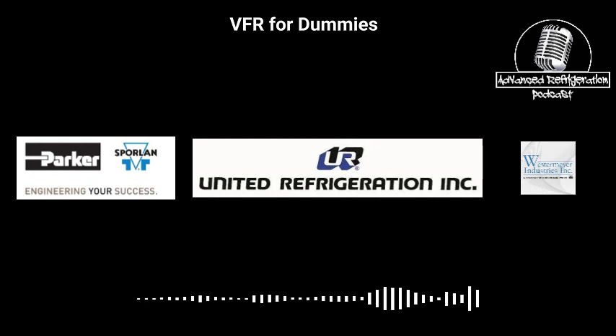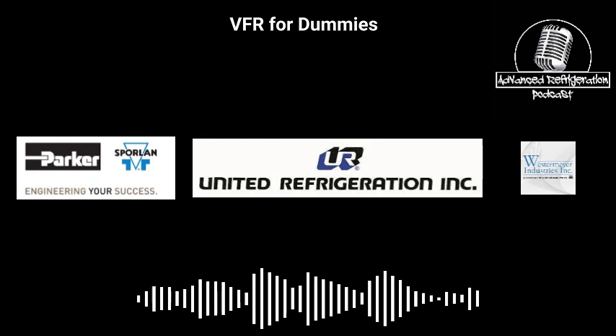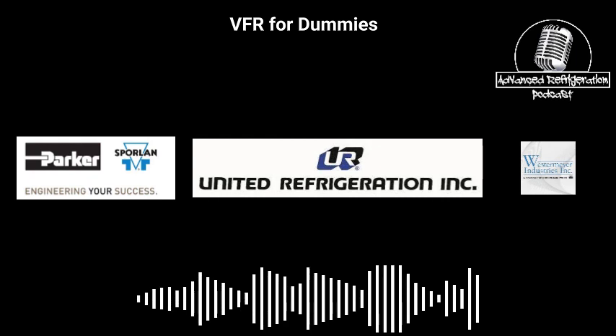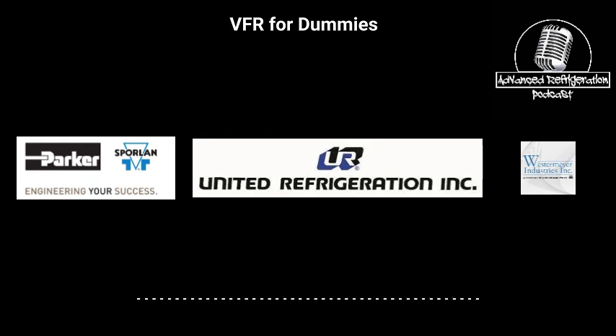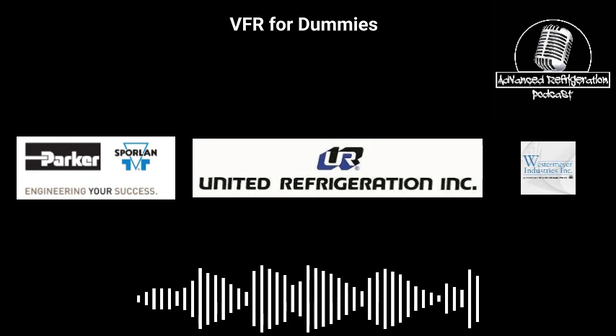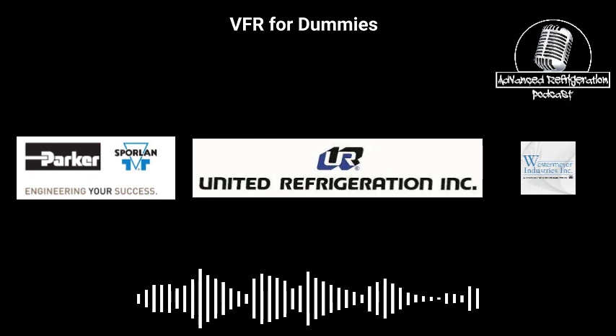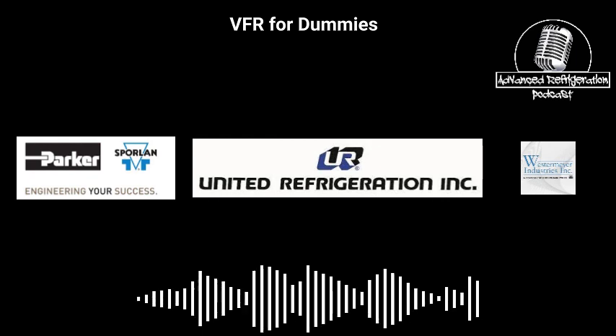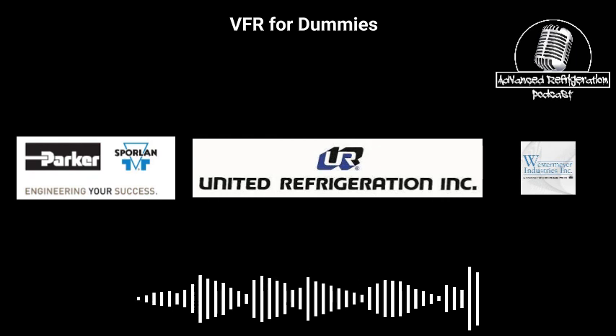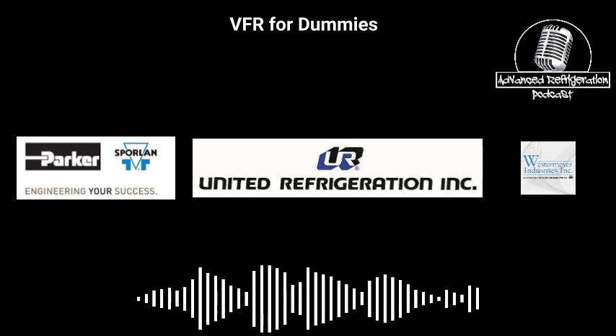Yes. But to that point, in 8 years, I've seen one box have an internal failure, and I'm pretty sure it was because it was dropped. For the most part, it's just controlling flow, right? So it's either opening or closing. You know what I mean? Yep. There's no temperature sensors or anything in there. It's just opening up all the way. So it's not like an electronic expansion valve where you're cycling all the time. And right, sometimes when it's cycling for heat, it's just going to stay on heat all year round, potentially.